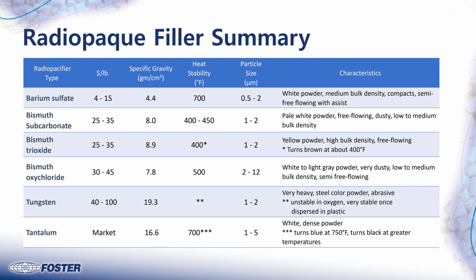And then, certainly the heavyweight champ is the tungsten, very high density. Downside is, you can get black or gray as the color. Very difficult to put a pigment in it because it is a steely gray powder to start off with. You can get very high loadings because it has a high specific gravity. You tend to see this in the tip of a catheter, where you want to really light up the tip. Because tungsten tends to degrade the performance of many of the polymers, especially in high loadings, you might want to limit it to a smaller portion of the catheter. We don't see too many catheters, the entire catheter, made with a tungsten compound.